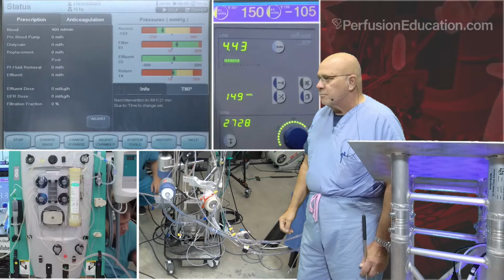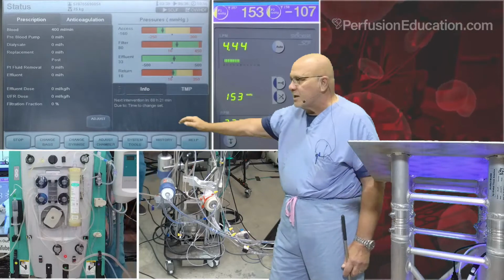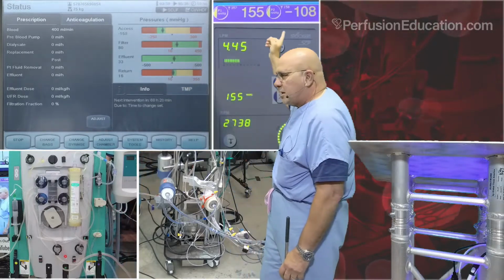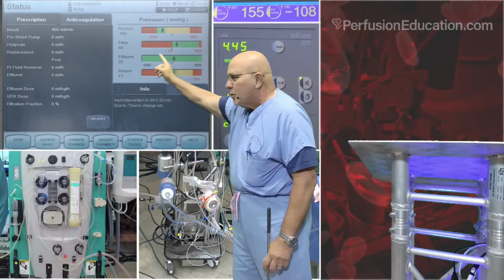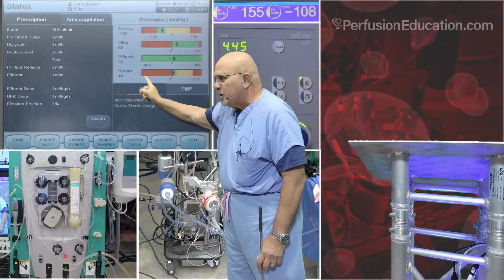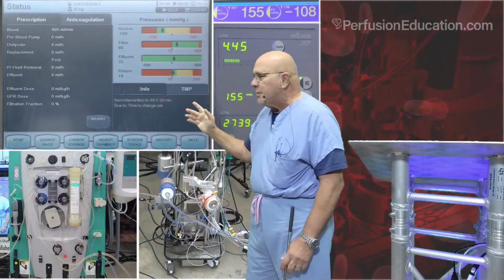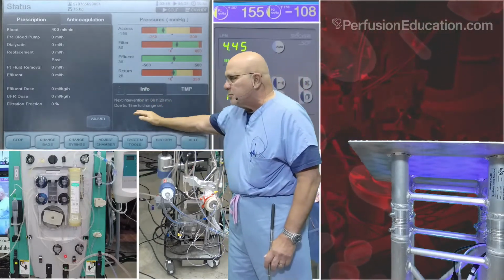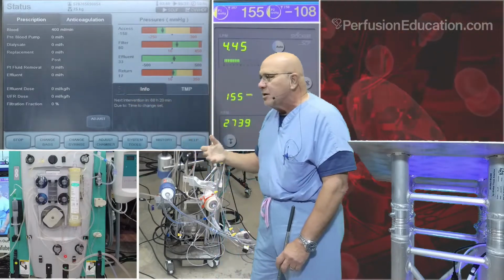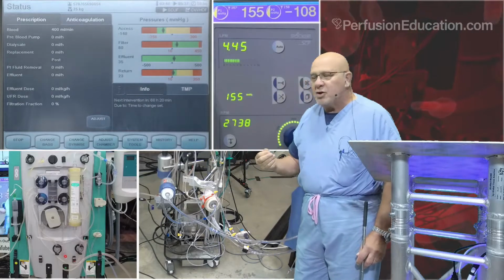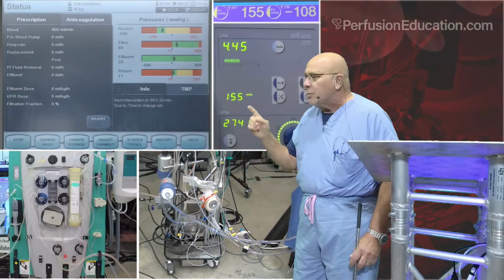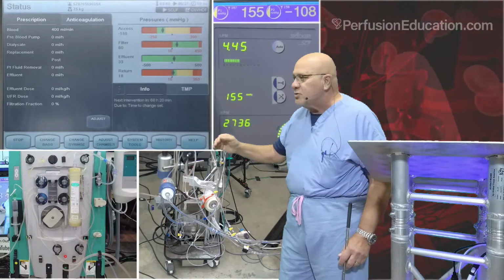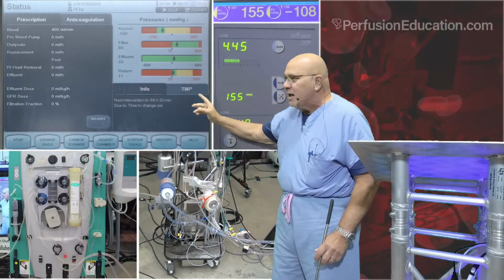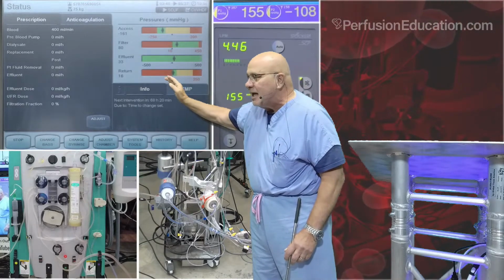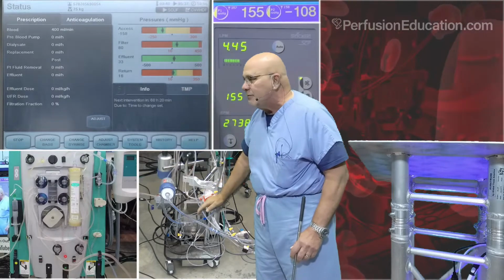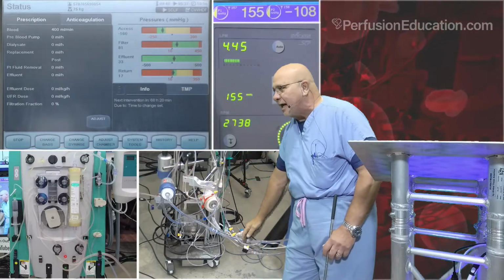That's good. That's close enough. There you go. So we actually decreased our access. Of course, we decreased our access pressure on the circuit as well. We increased our effluent pressure and our return pressure. So if you think about it, currently, other than this pressure being a little on the low side, these are not that dissimilar to what you would ordinarily want to see. But I want to show you what happens when you close the recirculation line off and you're depending on the machine to overcome the pressure of the circuit without that recirculation line that I have in place.